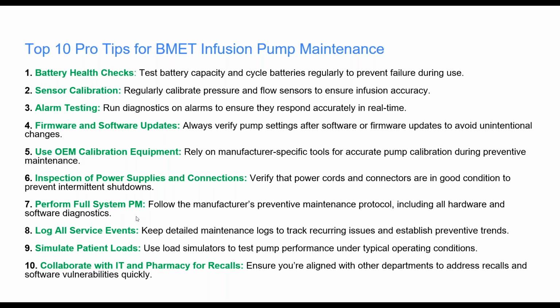When it's not ideal - sensor calibration, I already mentioned this, but make sure you calibrate those pressure sensors, those flow sensors, the detectors for whether or not there's - the optical detectors, typically for fluids.